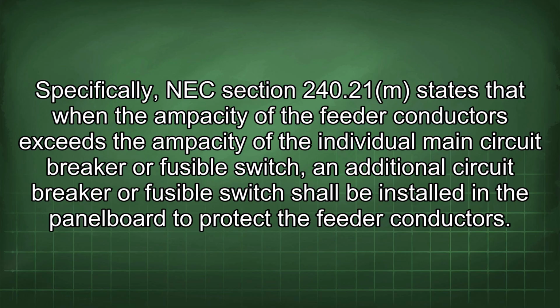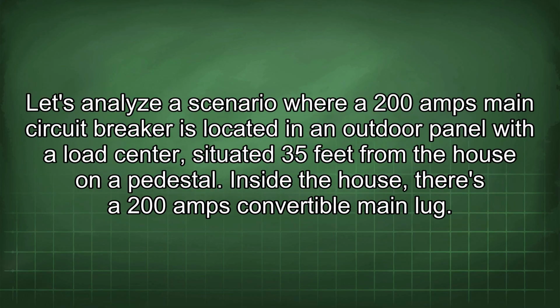Specifically, NEC Section 240.21 states that when the ampacity of the feeder conductors exceeds the ampacity of the individual main circuit breaker or fusible switch, an additional circuit breaker or fusible switch shall be installed in the panel board to protect the feeder conductors. Let's analyze a scenario where a 200 amps main circuit breaker is located in an outdoor panel with a load center situated 35 feet from the house on a pedestal. Inside the house, there is a 200 amps convertible main lug.